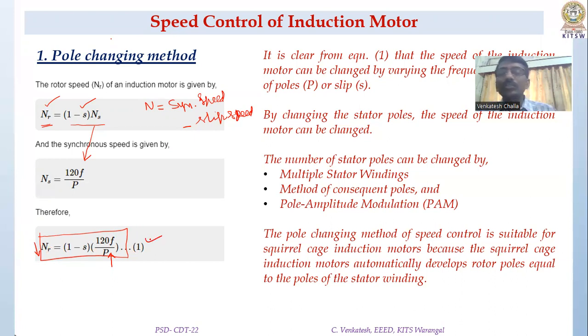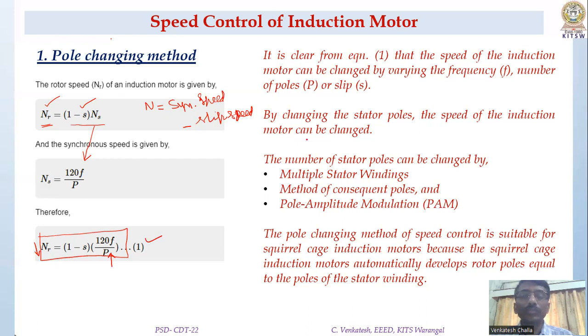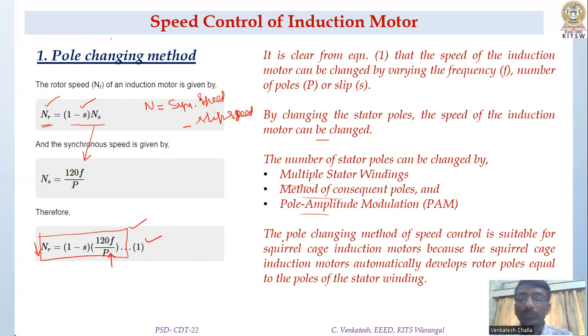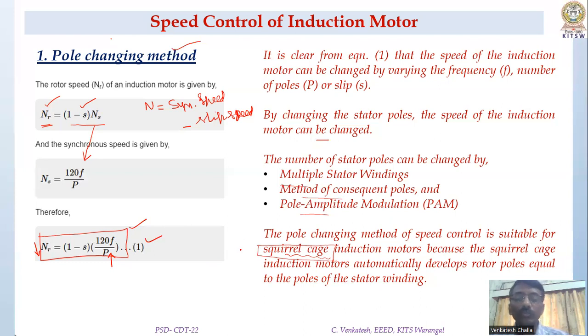By changing the stator poles, the speed of the induction motor can be changed. There are three techniques to obtain this change in poles: multiple stator windings, method of consequent poles, and pole amplitude modulation. The pole changing method is suitable for squirrel cage induction motors because the squirrel cage rotor automatically develops the same number of poles as the stator — no arrangements at the rotor side are needed, which simplifies the speed control method.